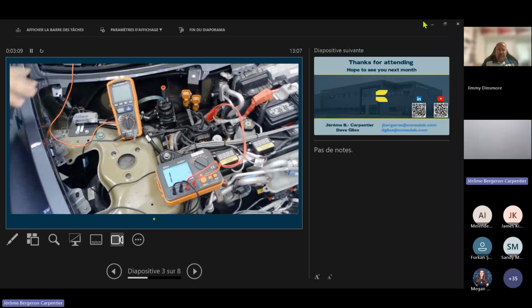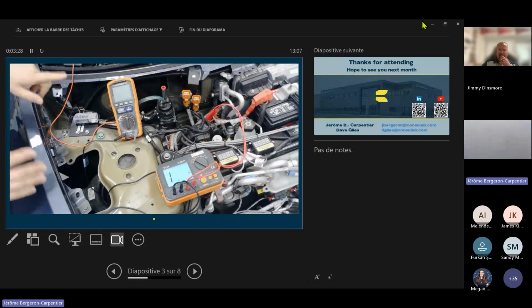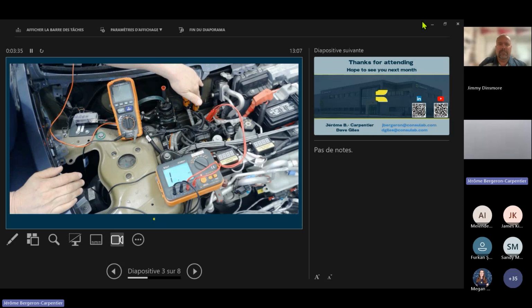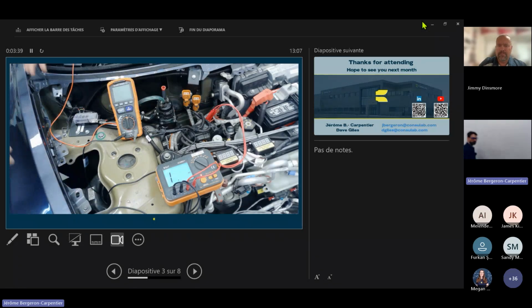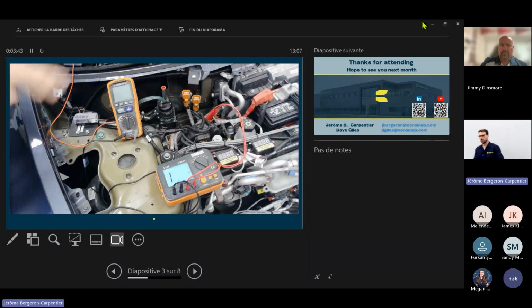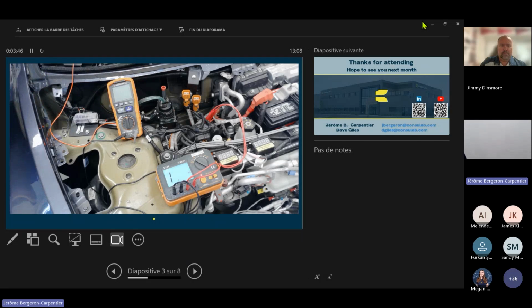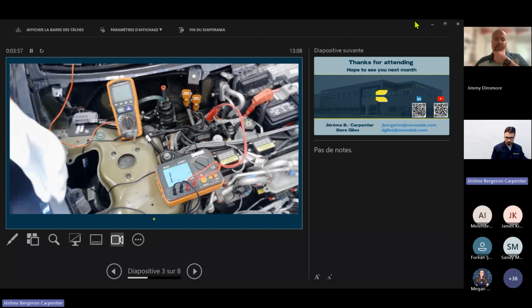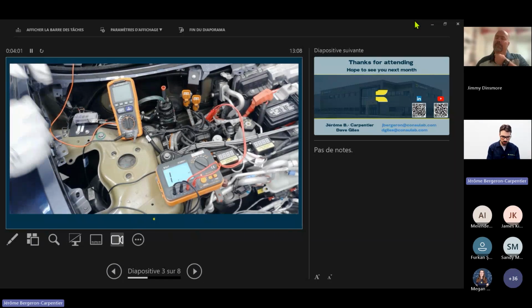As you can see, I have disabled the high voltage system on this vehicle. I've done the procedure to do a service disconnect. I disconnected the negative terminal of the battery, and I just want to go through a real quick test with this vehicle. Now, I'm not going to go into the full diagnostics with this one here, but I do want to show something that's very important when we have an isolation fault. We do have a disconnected high voltage connector here. We powered it down and tested. There's no high voltage in the system. We tested the connector, no high voltage. But now we want to do an isolation test to find out where the fault may be, whether it's within the unit itself, and so on. There are lots of different specifications on testing high voltage compressors. Some of them are 250 volts, 500 volts, and so on. So what we're going to do is a test on this compressor.